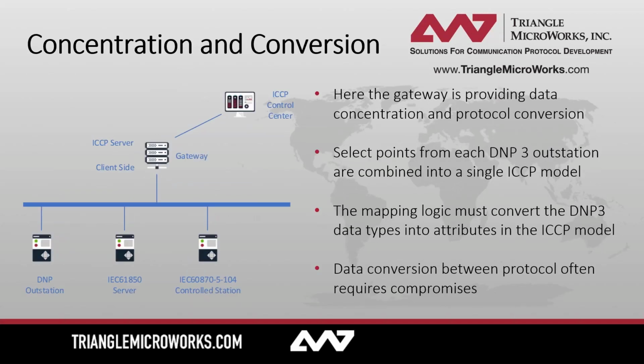If your upstream control center is using a different protocol than the local substation, some gateways can act as both a data concentrator and a converter at the same time. This allows the important bits of your substation to be sent up to the control center. In this specific situation, we have a DNP3 outstation, a 61850 server, and a 104 controlled station, all being mapped and translated to an ICCP database within the gateway, and then that is exposed up to the ICCP control center.